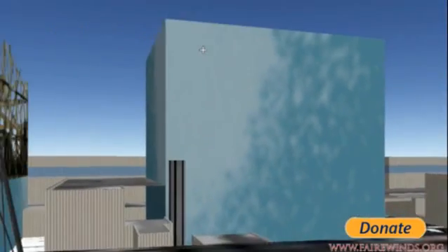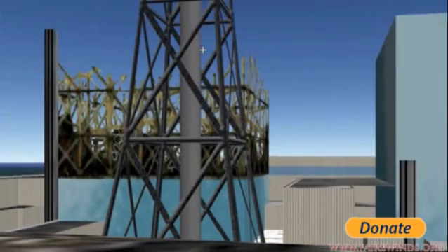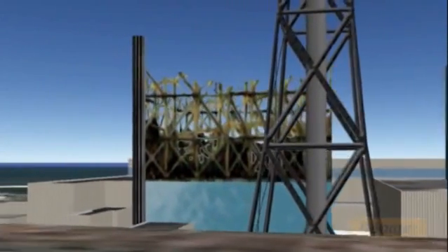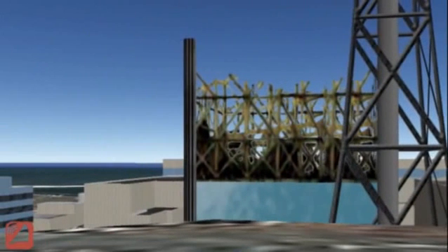Now remember, these power plants have basements that are essentially below sea level. And the water on the hill, that's just coming out of the hill as groundwater, had been coming out for 50, 60, 1,000 years. When they built the power plants, they had sump pumps in the basement that pumped that water out so that the basements would stay dry. Well, now, of course, the basements are radioactive, so they can't pump it out. So we've got hot radioactive material in these basements, and it's got no place to go except downhill into the Pacific Ocean. The problem number 3 is not the leaky tank farm.